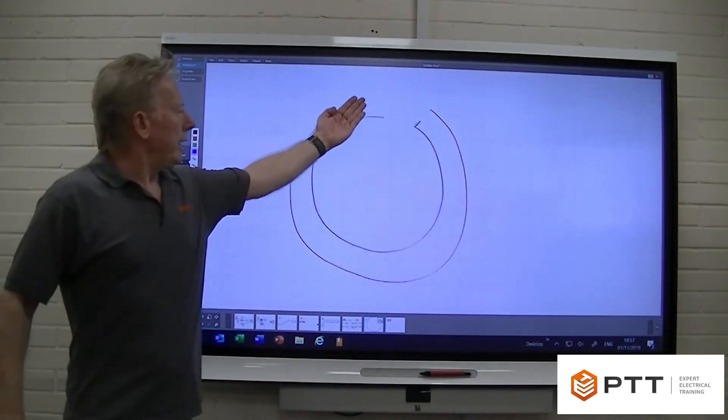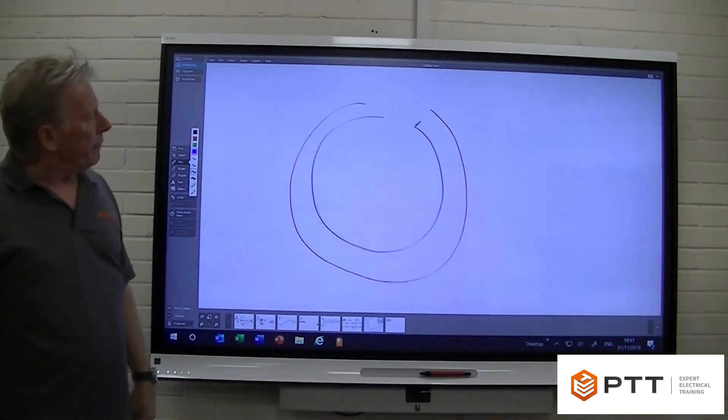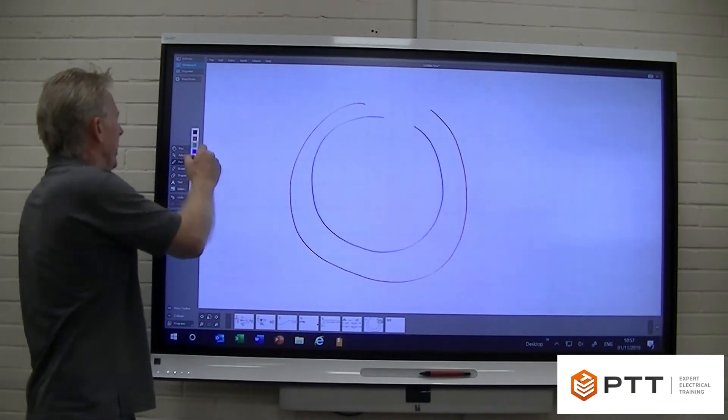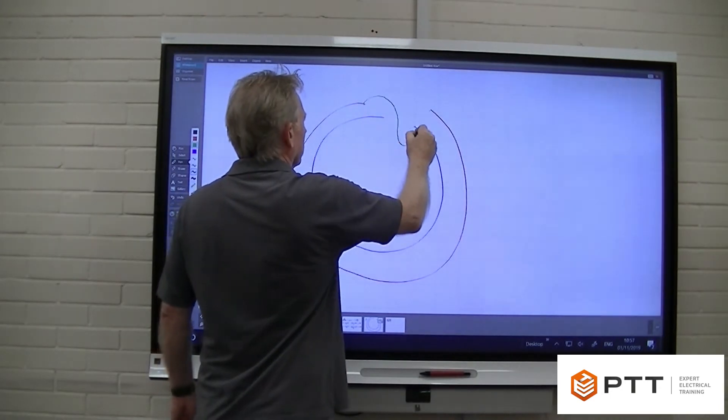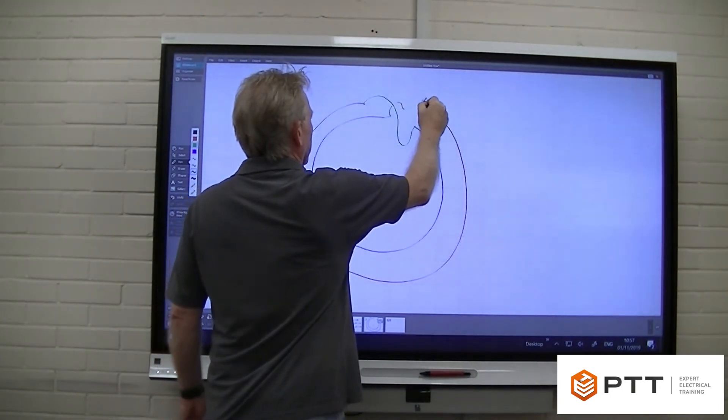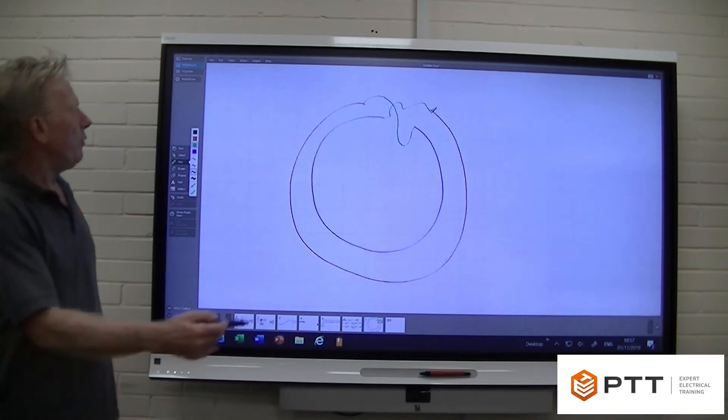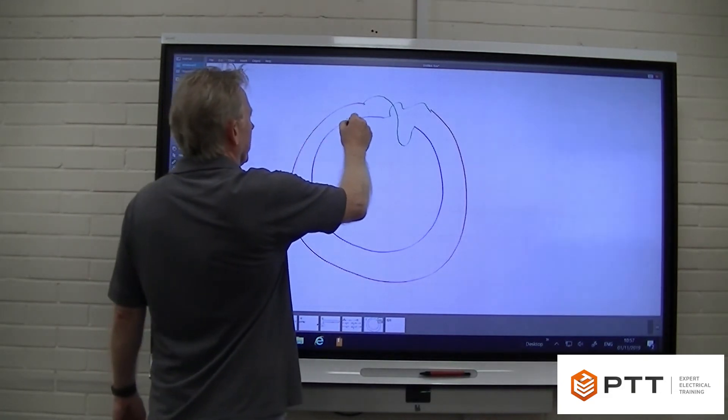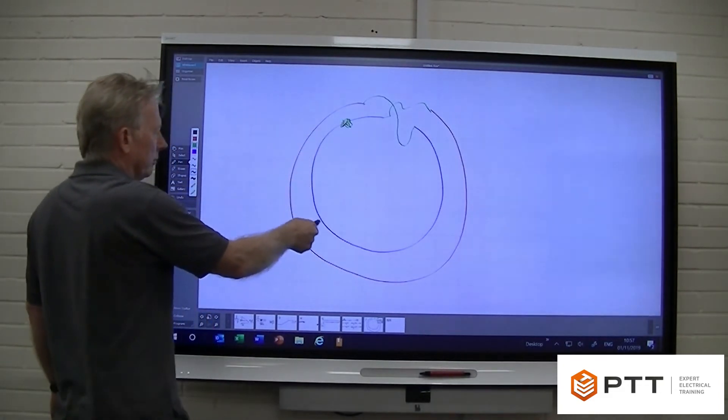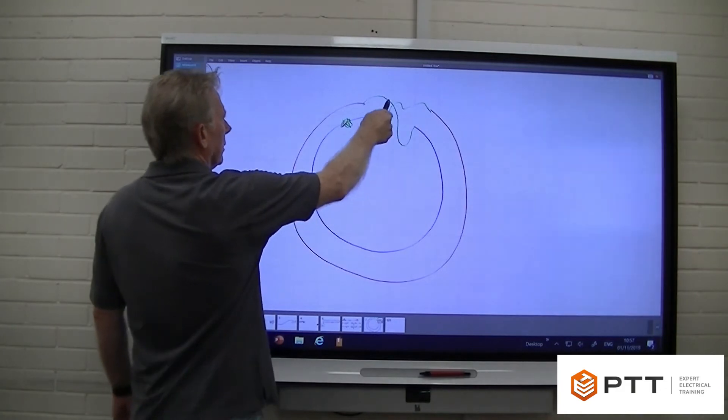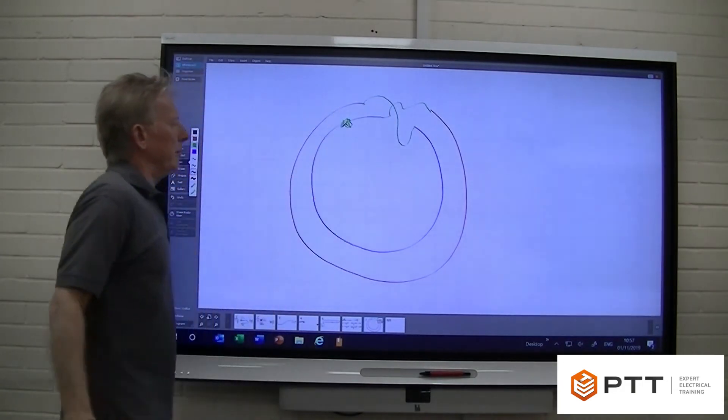Notice that we've already done the end-to-end tests, so we've proved it is in fact a ring. And we're going to make a figure-of-eight cross connection so that we create an equal resistance all the way around. So we are going to do that – you can use crocodile clips or a connector, whatever is convenient. And if we pick a point on the ring, let's just pick that point there. If we follow all the way around, you can see we have in fact created one gigantic loop of cable.